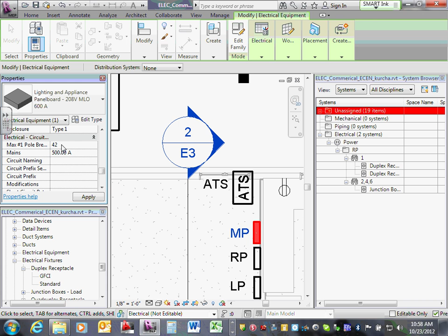Does it? Yeah, yours does? Then you dropped the wrong panel. Okay, does it give you a 208 option? Okay, then we have to go change your panel. Not a big deal, everybody else's panel shows 208. Yeah, when we drop the panel, guys, it gives you a decision. You have to make it 208 or 480 from the get-go.